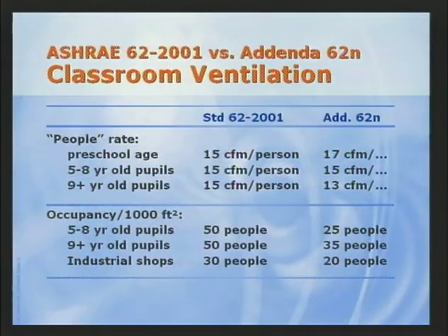But what about situations where the design occupancy may not be known? Addenda 62N lists default values based on typical occupant density. Using that approach, we see that the outdoor airflow rate for classrooms with 5 to 8-year-old students is 15 CFM, which is really unchanged from the previous standard.